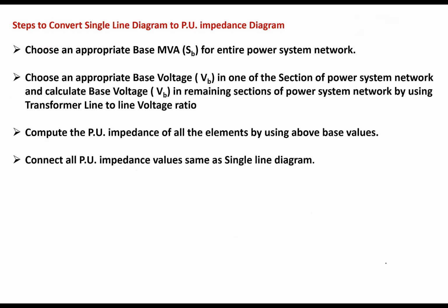Next. The next topic in our discussion is how to convert a single line diagram into a per unit impedance diagram. The first step is, for the entire power system network, choose a common base MVA. Next, choose an appropriate base voltage in one of the sections of the power system network and calculate the base voltage in the remaining sections by using the transformer line to line voltage ratio. Very, very important point: the power system network will have only one base MVA, but it will have different base voltages and different base currents. So in one of the sections, choose an appropriate base voltage and calculate the base voltage in the remaining sections by using the voltage transformation ratio of the transformers.